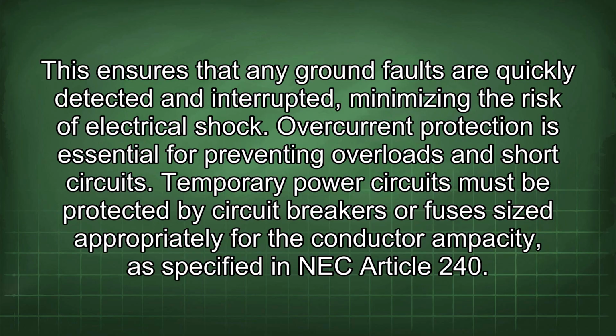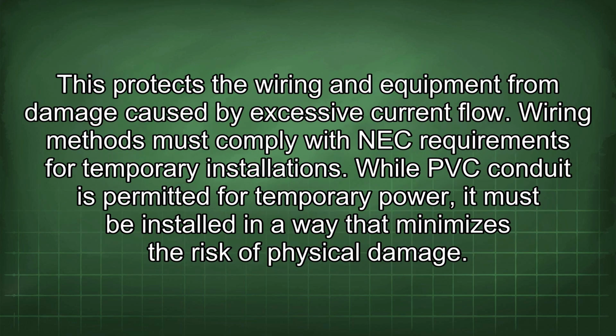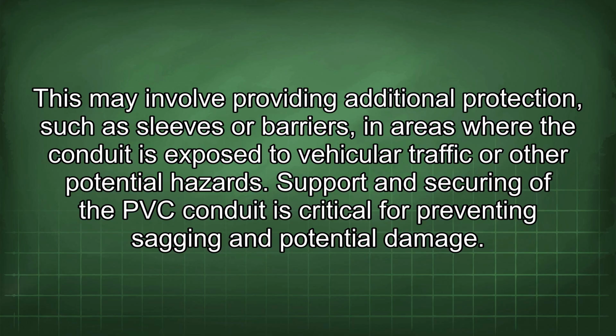Overcurrent protection is essential for preventing overloads and short circuits. Temporary power circuits must be protected by circuit breakers or fuses sized appropriately for the conductor ampacity as specified in NEC Article 240. This protects the wiring and equipment from damage caused by excessive current flow. Wiring methods must comply with NEC requirements for temporary installations. While PVC conduit is permitted for temporary power, it must be installed in a way that minimizes the risk of physical damage. This may involve providing additional protection, such as sleeves or barriers, in areas where the conduit is exposed to vehicular traffic or other potential hazards.